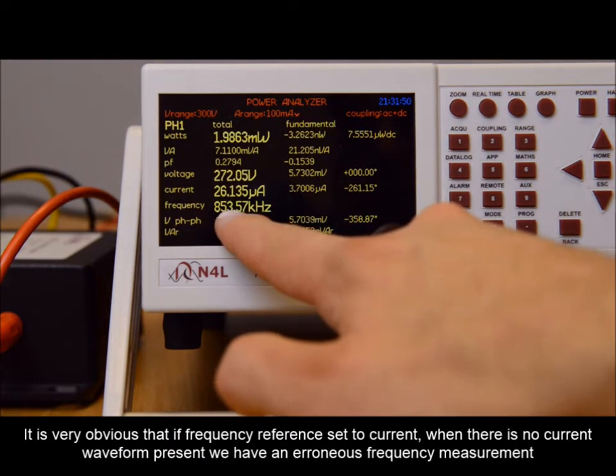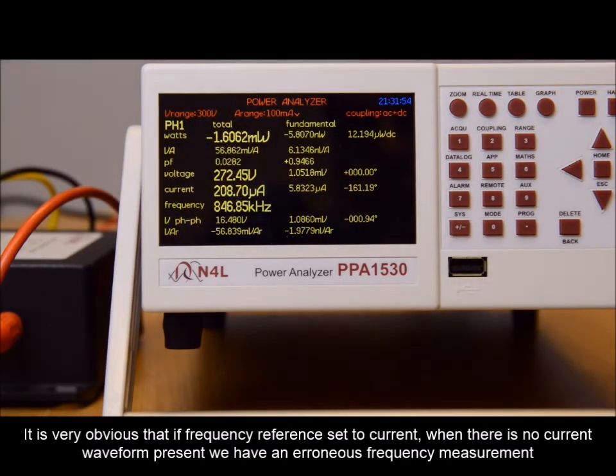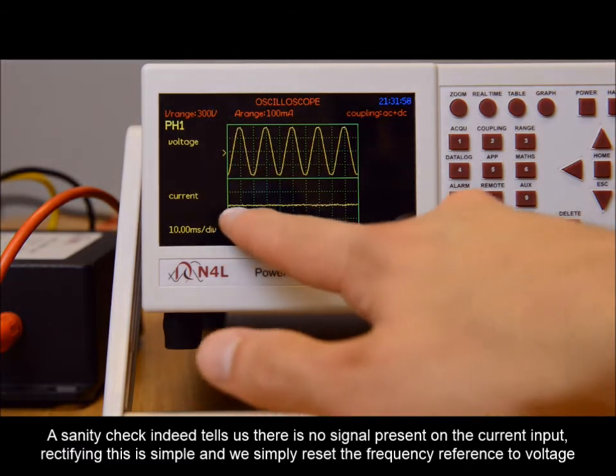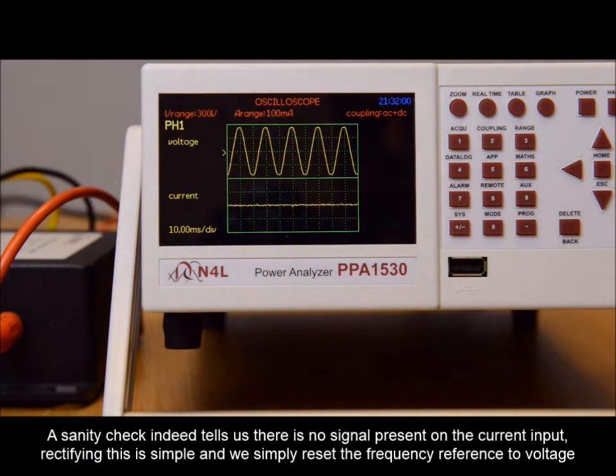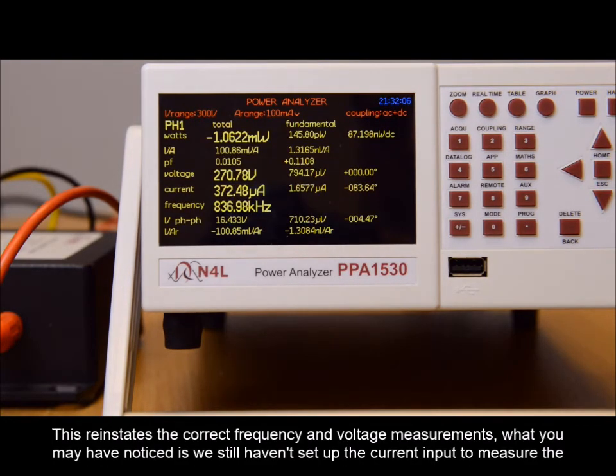It is very obvious that if frequency reference is set to current when there is no current waveform present, we have an erroneous frequency measurement. A sanity check indeed tells us there is no signal present on the current input. Rectifying this is simple, and we simply reset the frequency reference to voltage. This reinstates the correct voltage and frequency measurements.